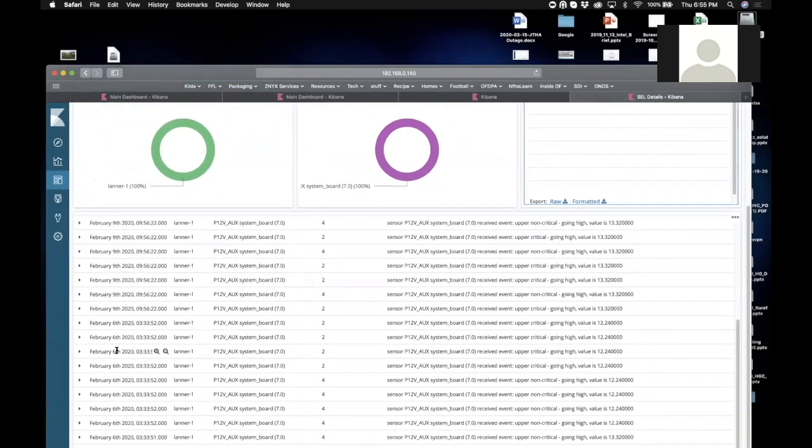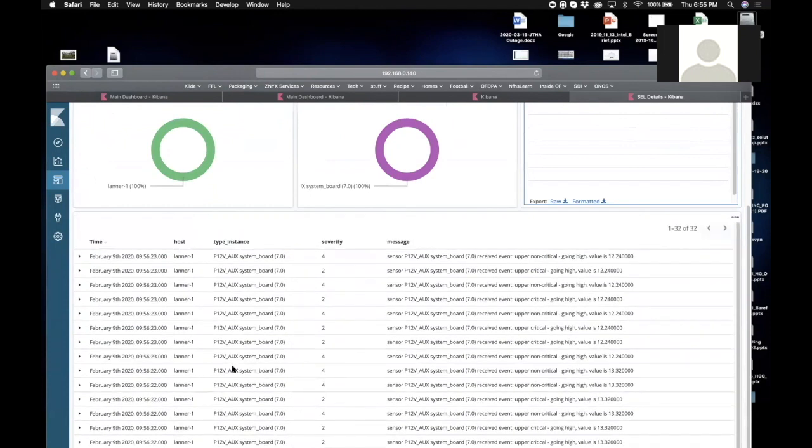These two events may have been a power supply that you plug in, and while the power is stabilizing, you had a slight over-voltage situation that was maybe caused by a transient inrush current, and it went away. So it lasted less than a second, and it returned to normal. So I don't really think this is an issue.